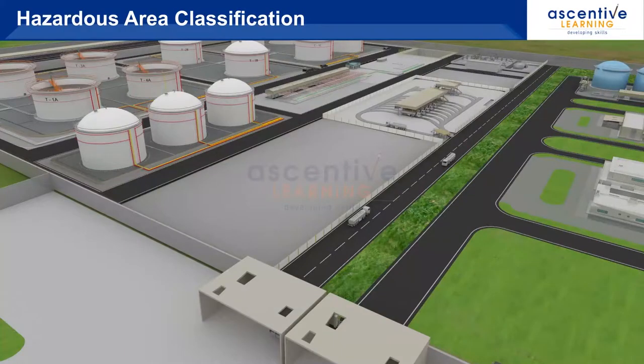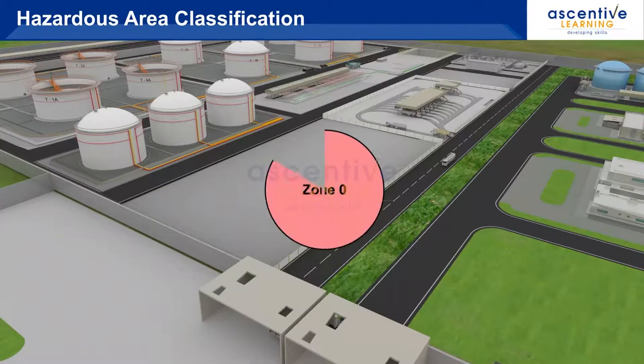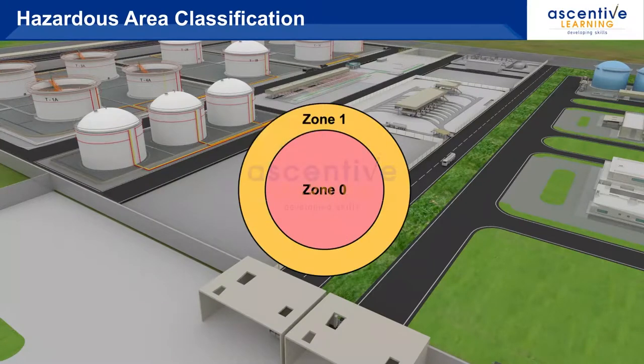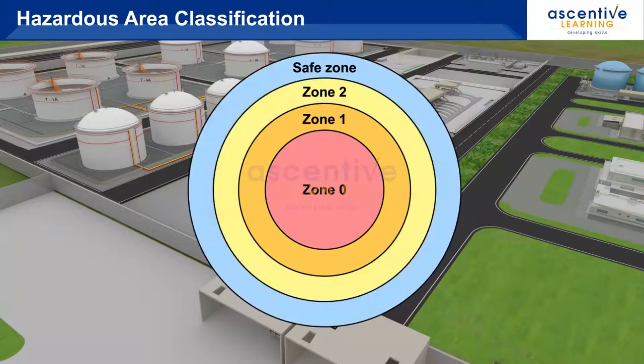Hazardous areas are classified into three different zones — Zone 0, Zone 1 and Zone 2 — based on an assessment of the frequency of occurrence and duration of an explosive gas atmosphere.